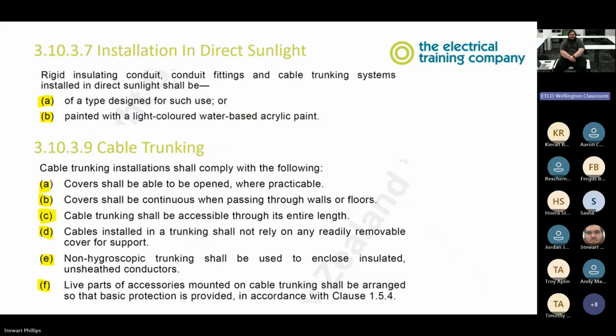Non-hygroscopic trunking shall be used to enclose insulated unsheathed conductors. But what does non-hygroscopic mean? Doesn't like water? Yeah. Yeah, so it does not absorb water, whether from water readily accessible or water in the atmosphere. So unsheathed conductors, insulated but unsheathed. So conduit wire. Cool. Live parts of accessories mounted on cable trunking shall be arranged so that basic protection is provided in accordance with 1.5.4. So that's your PowerPoints mounted to the trunking.